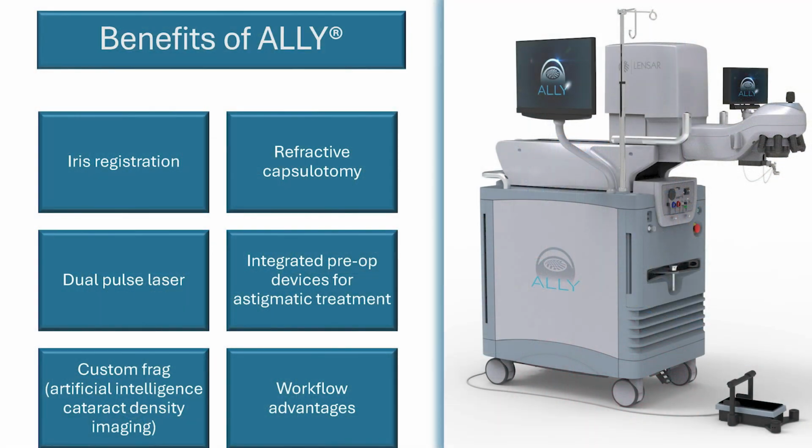This is the unit that we're using. There are many different types, several different models, but this happens to be the latest generation and quite frankly the most sophisticated, and it does produce the ability to very accurately place the implant for a toric correction. It uses 6 Scheimpflug cameras. Importantly, it registers both the cornea, the lens depth, and interestingly, the lens density itself.